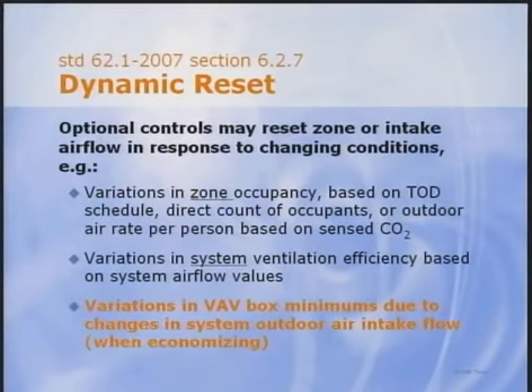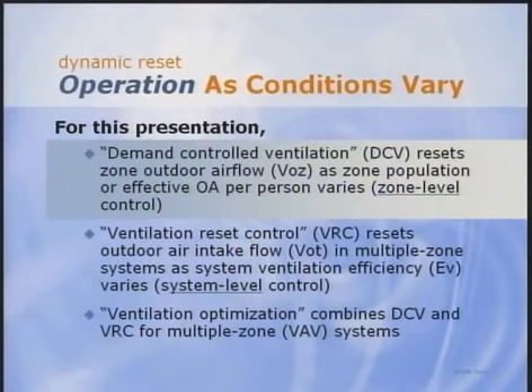allows dynamic reset. Optional controls can be used to reset either the outdoor air intake or the zone airflow, or both. These controls respond to changing conditions such as variations in zone occupancy, system efficiency, or outdoor air intake during economizer operation. We'll talk about the first two of these, starting with variations in zone occupancy. Actual population changes the demand for ventilation, so control approaches that adjust zone outdoor airflow in response to current population are often called demand-controlled ventilation. But before we discuss operating options further, let's look at design requirements.